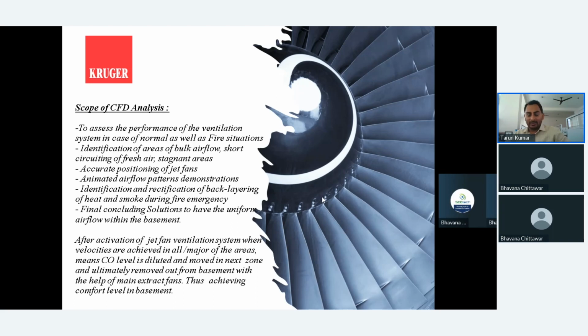In CFD analysis, we identify areas of bulk airflow, short circuiting of fresh air, and stagnant areas. We also do accurate positioning of the jet fans. Jet fans always work on a pull and push system. Wherever a fire happens, for that particular location the jet fan will be switched on, as the signal goes through the CO sensor to the panel.